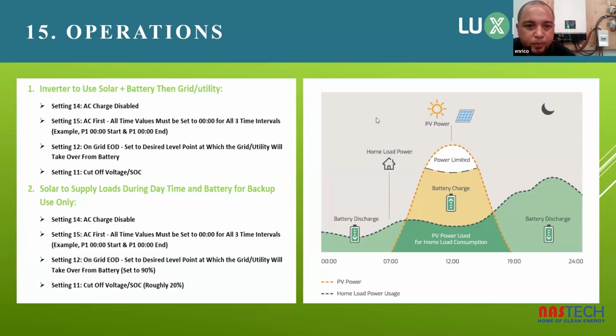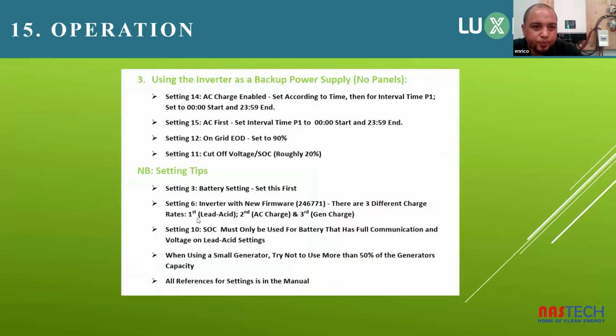Setting up the inverter. So now this is the setup for the inverter. When setting up the inverter, as I mentioned in the beginning, you first need to set setting 2, that's your PV, your solar. Setting 3, your battery settings, set first. Those are the 2 that you first set. Checking your firmware is another tip. And setting 10 SOC must only be used for battery that has full communication and voltage on the lead acid settings. That's with regards to charging and discharging.